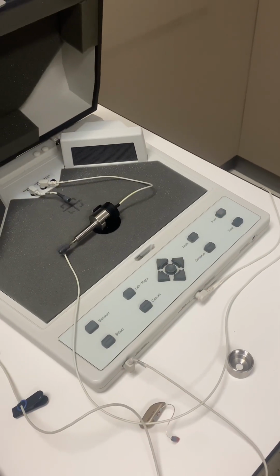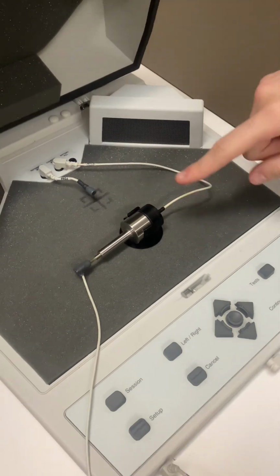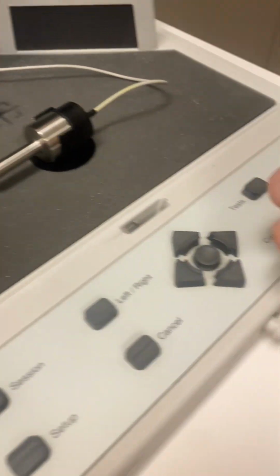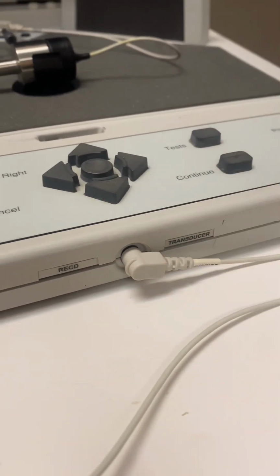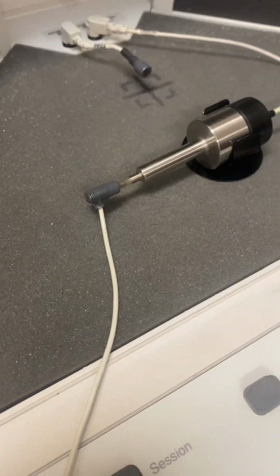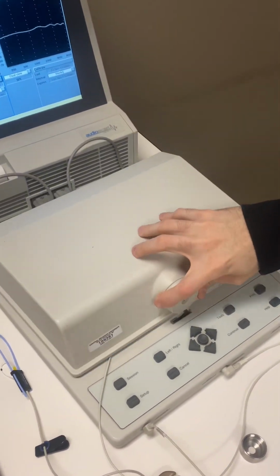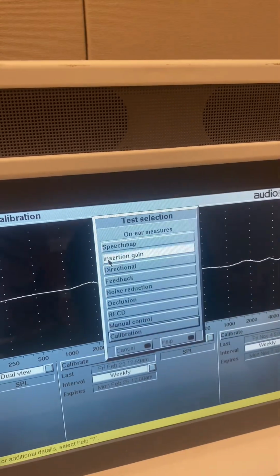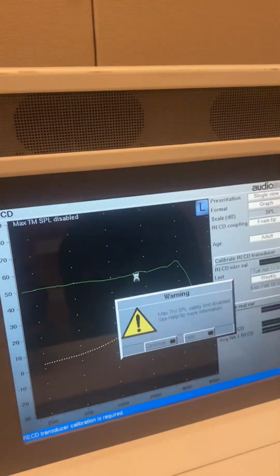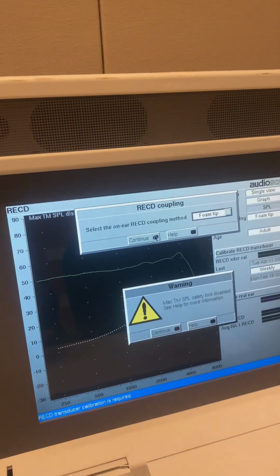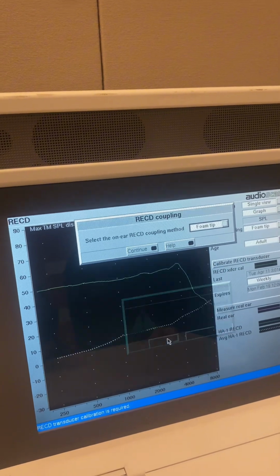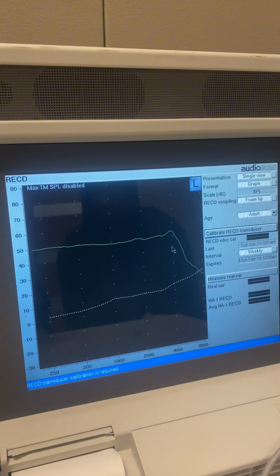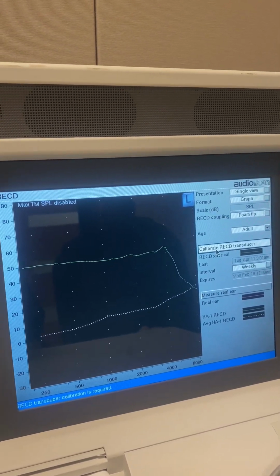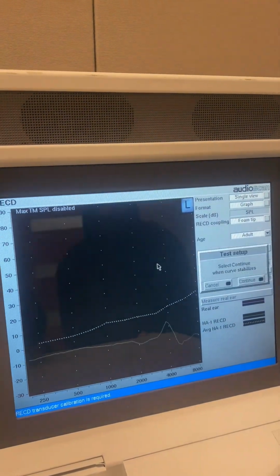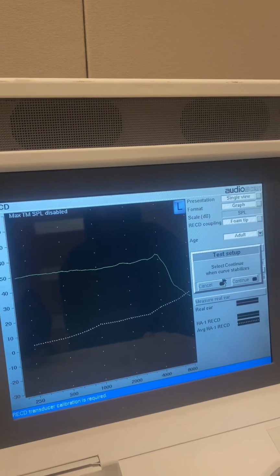Okay. Make sure the BTE coupler is attached to the coupler mic, and then make sure the RECD transducer is attached to this slot called transducer, and then you want to make sure to connect it to the end of the BTE coupler, and then you're gonna close up the test box. You're gonna hit test. You're gonna hit on-ear measures. You're gonna hit RECD, and then you're gonna have to make sure foam tip is selected. Hit continue. And then we're gonna hit calibrate RECD transducer. And continue. And there you go.